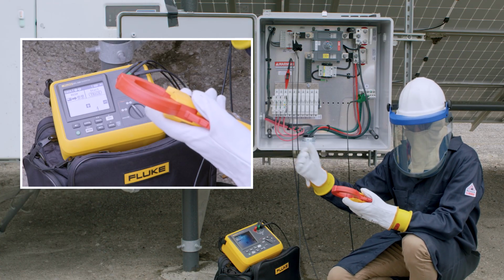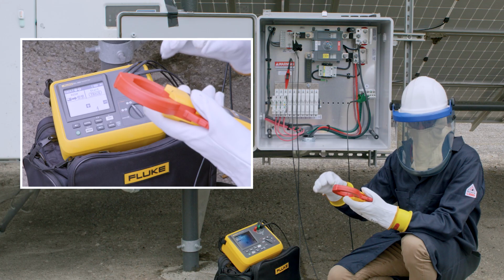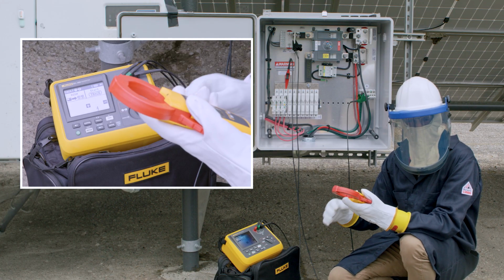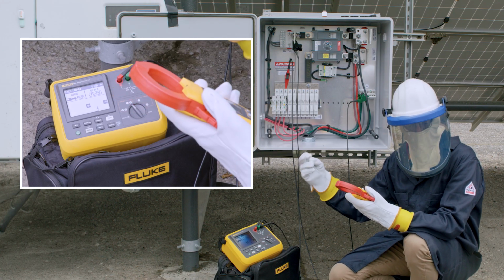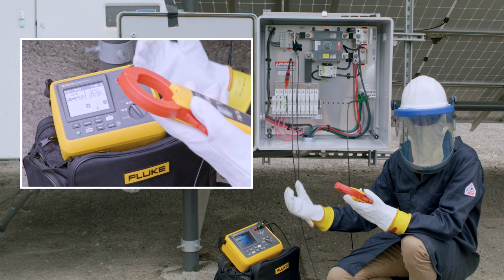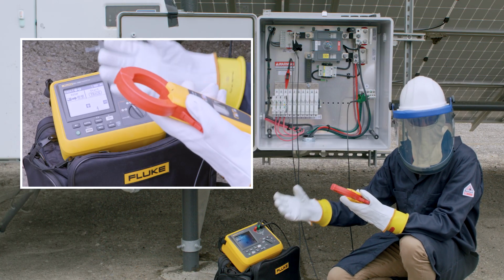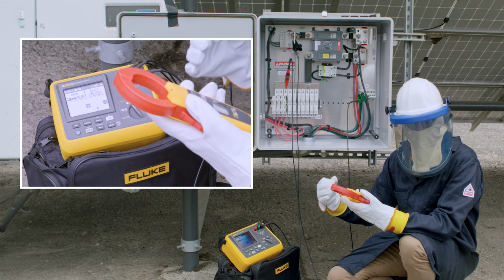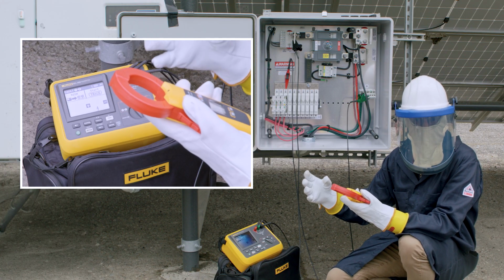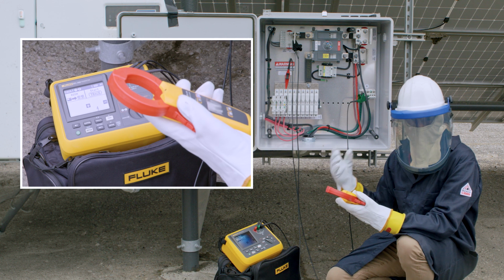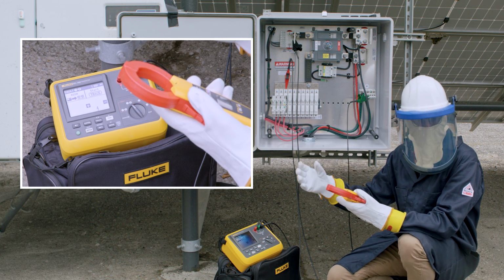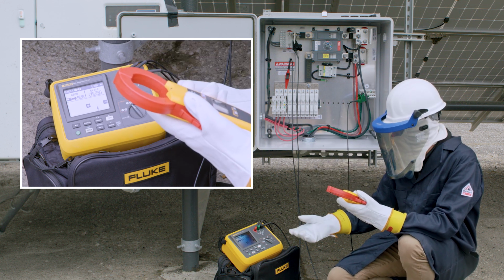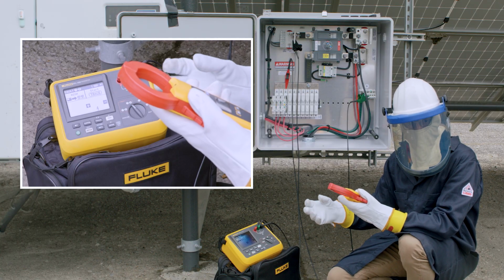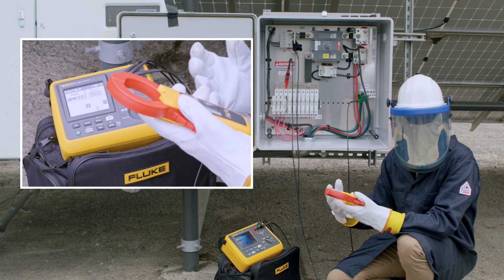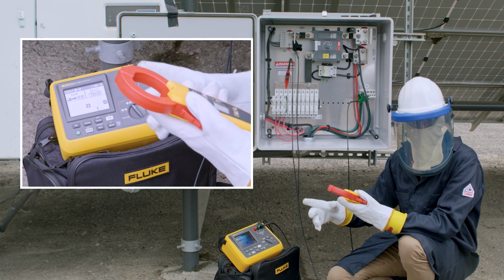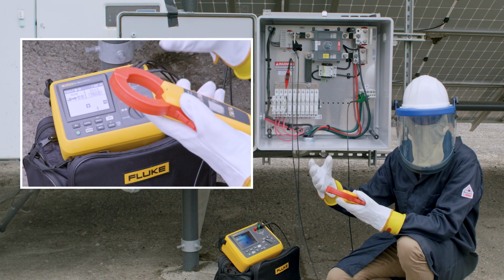So the difference between high and low mode is really related to whether you're seeing signal or not. If you're in high mode and when you were in analyze, you measured a high resistance fault, if you're not getting the signal in high mode, first thing you want to do is check and make sure that the unit is set up properly. Check at the test leads and make sure that you have signal there. And then switch to low mode. You can see the signal change and then go out and do your testing throughout the array. It might be easier to pick up that low signal than it was with high signal in a high resistance fault.